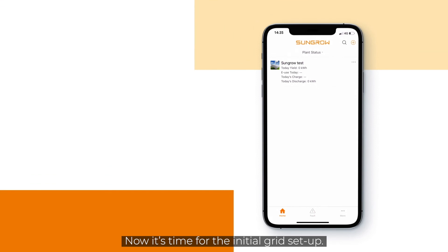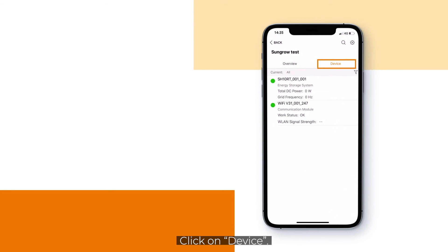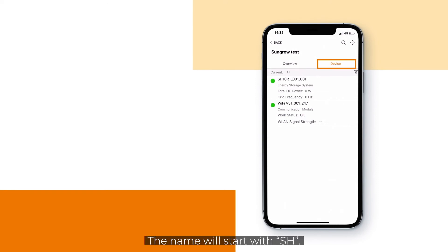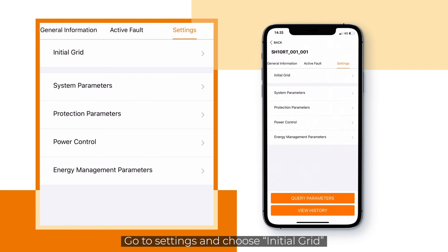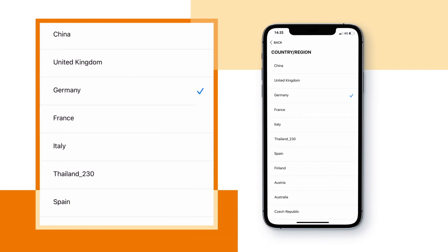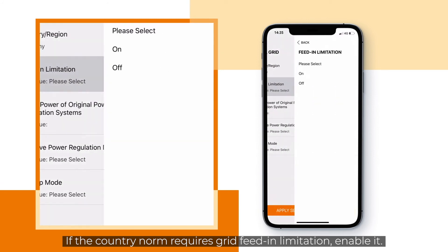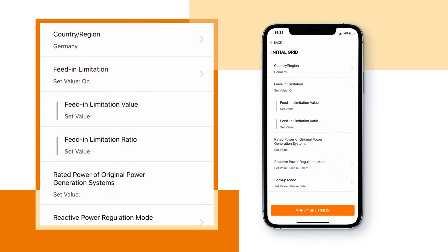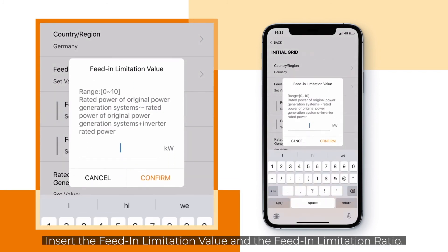Now it's time for the initial grid setup. Click on your newly created plant, then click on device. Choose the inverter — the name will start with SH. Go to settings and choose initial grid. Choose the country of the plant. If the country norm requires grid feed-in limitation, enable it. Insert the feed-in limitation value and the feed-in limitation ratio.